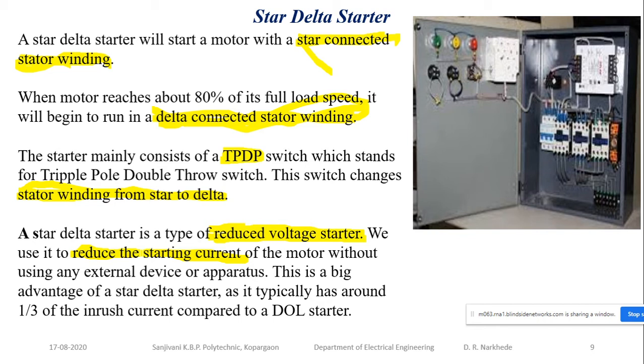Okay, if the motor's rated current is 5 amperes, when we start the motor it can take a current of up to about 30 amperes. Now why will it take that much high current? Because it has to establish the magnetic field. Definitely that current will be taken for a very small period of time, a fraction of a second only, but it will take that much current.